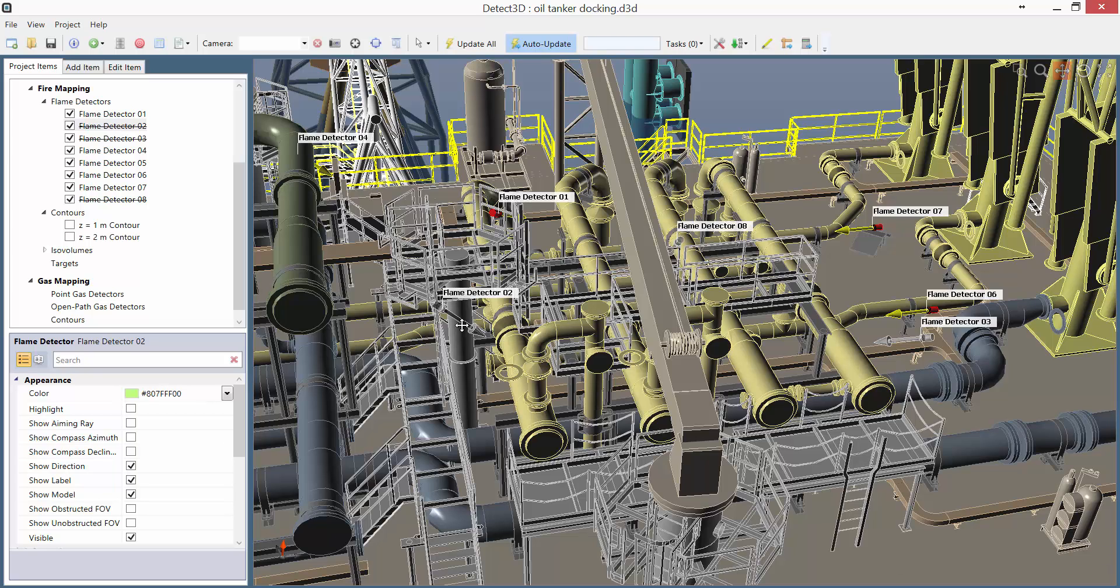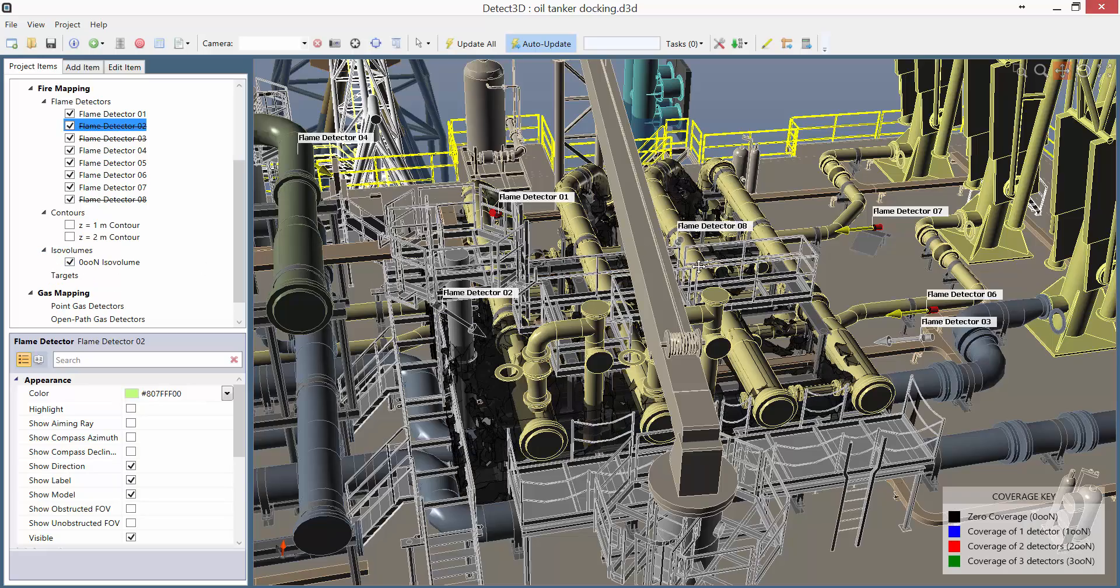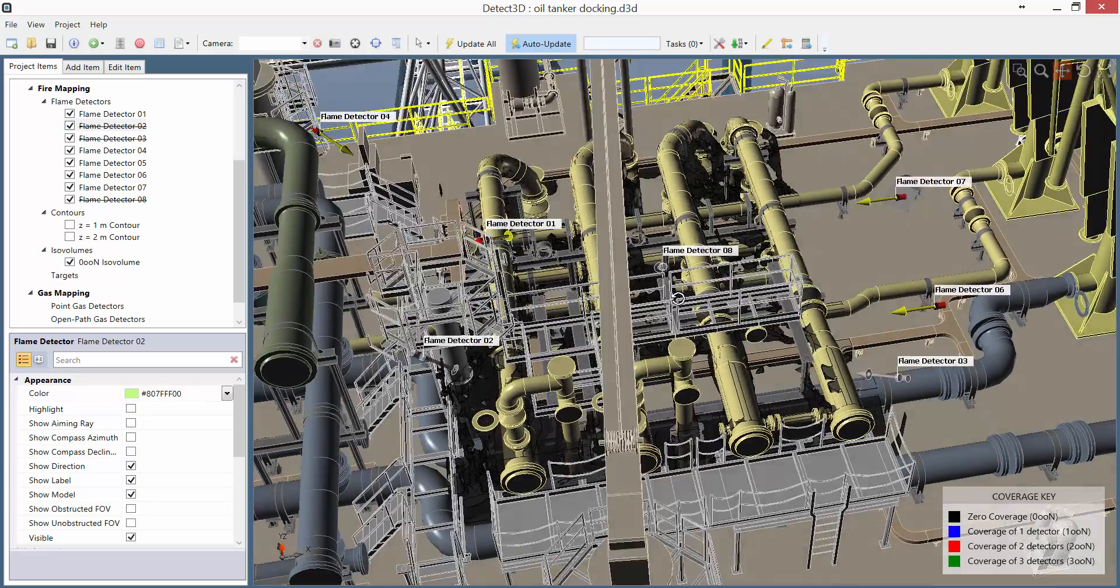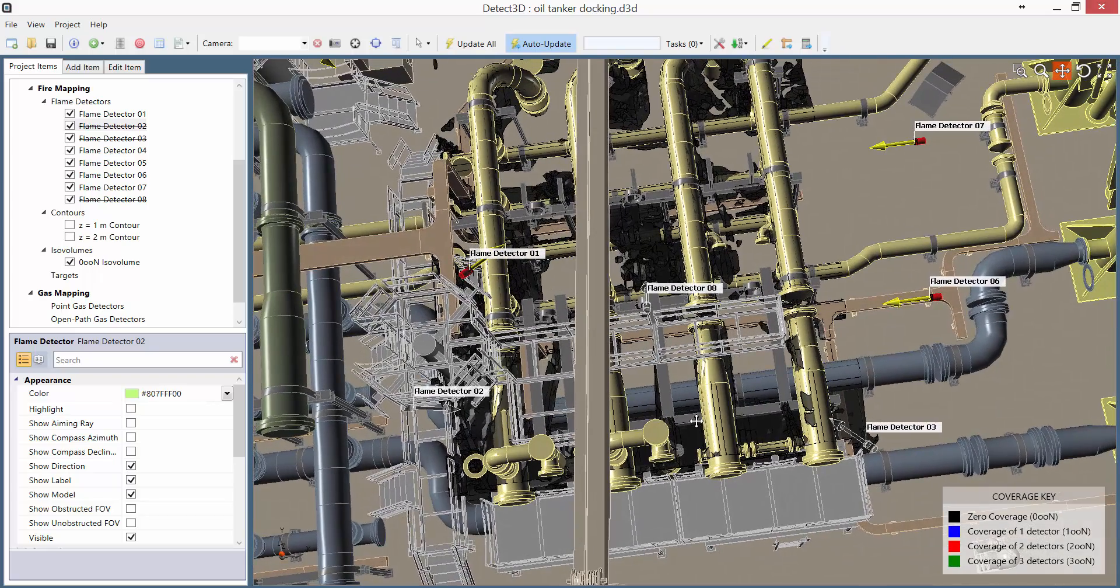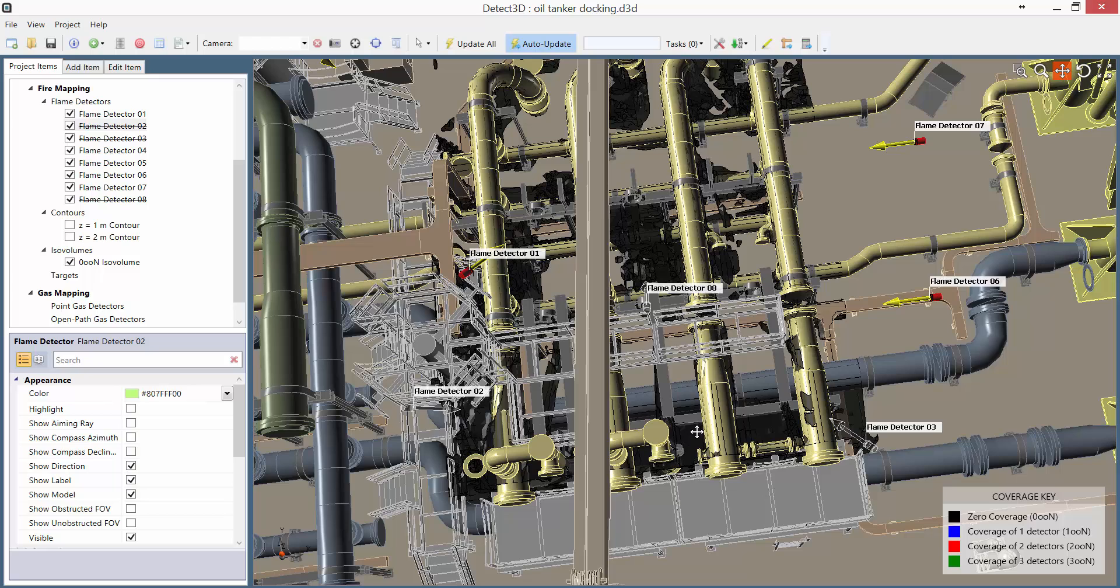Now while the detector ranking tool is very useful, it does not tell you where to put a new detector. So we need to look at the zero coverage isovolume, and we can see a couple of blind spots here. We also know that Detectors 6 and 7 have ranked particularly well on the ranking tool.